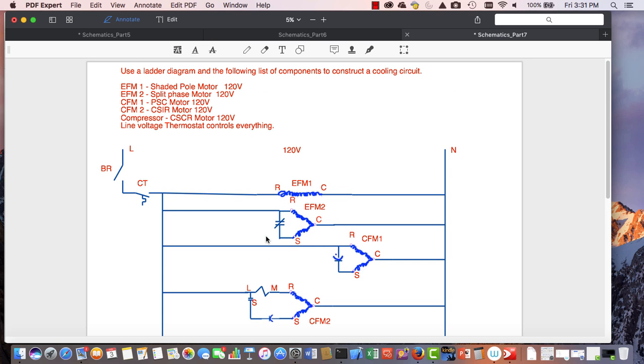CSIR motor, which is my CFM2, has a current coil relay, coil in series with the run. It's one of the few cases we'll see a coil in series with another load. And the only reason is because this coil doesn't use any voltage, basically. It's all based on current. And if you look at it, you'll understand why. The relay coil is very, very large. There's going to be no voltage drop on it. It's all current based. And then I have my start capacitor that's there as well.